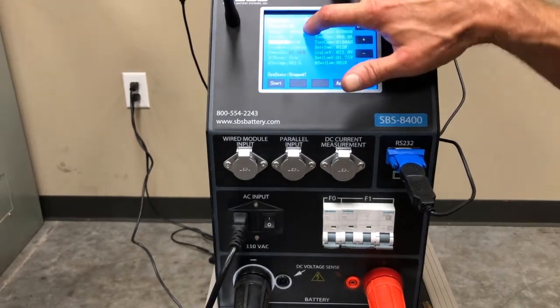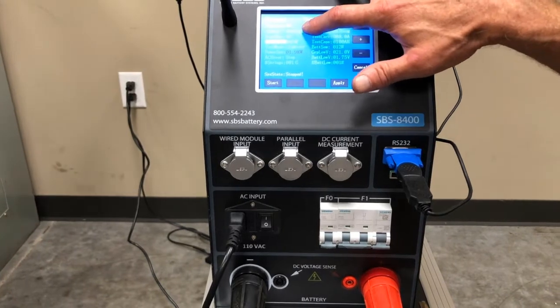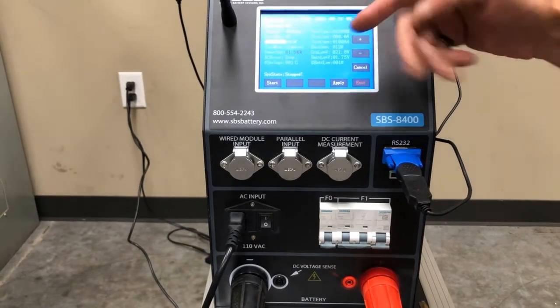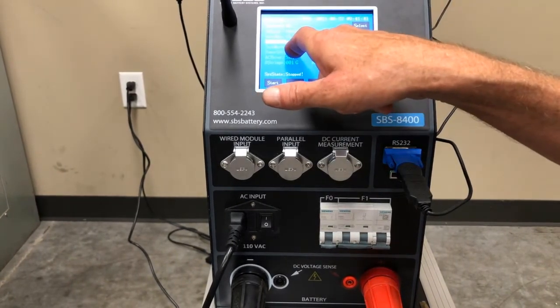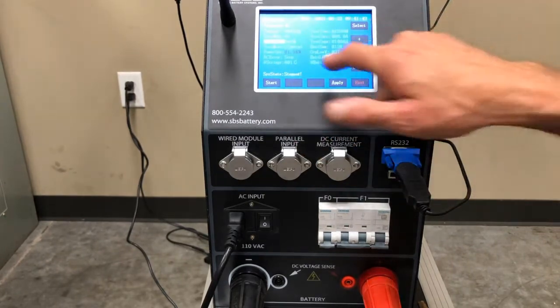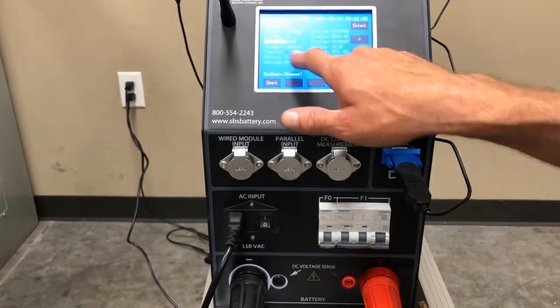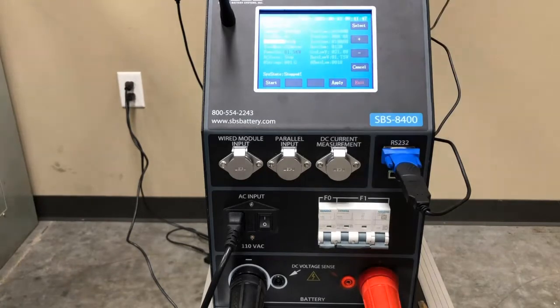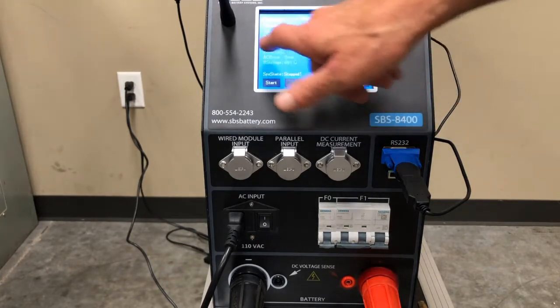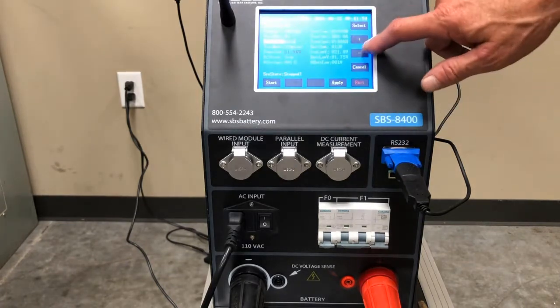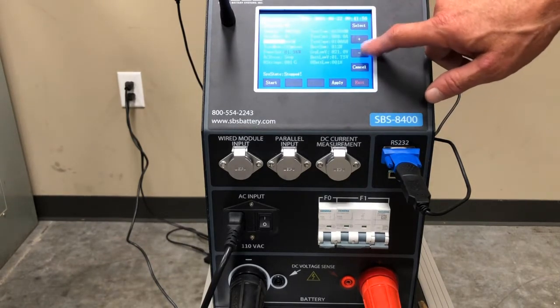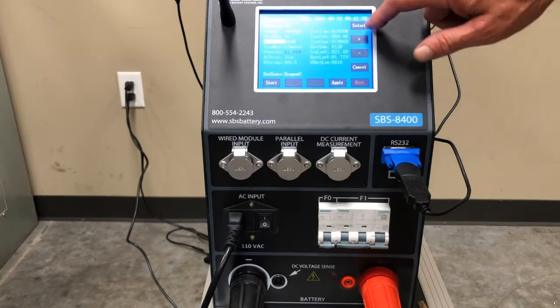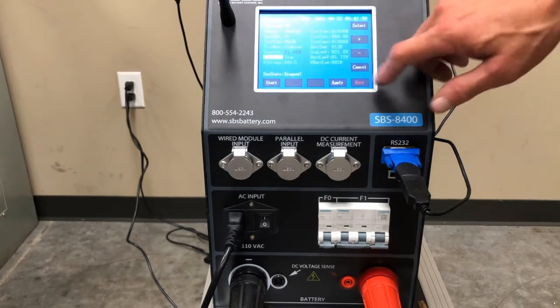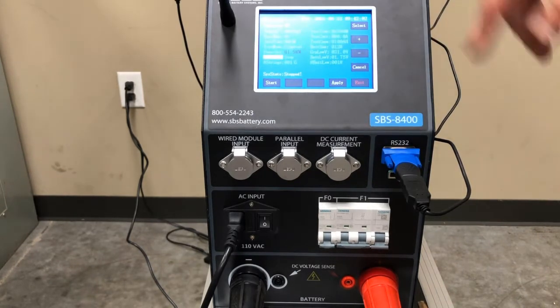I'm doing constant current discharge. So I want to make sure my test mode is in constant current. Power set is blacked out or grayed out because I'm not in constant KW. AC error. I'm going to scroll down to that AC error. I'm going to put that to pause, the same thing that I did in the setup screen.